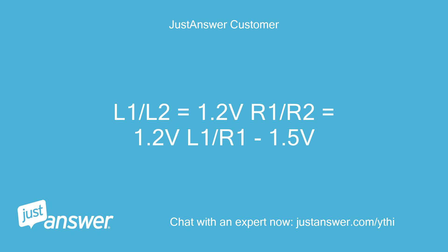Earlier you had stated that you had 63 ohms across the slip rings, which is good. But what I would like you to do is to leave the brush block installed, with the wires removed, and ohm across the brush terminals themselves. If you still get 63 ohms, the problem is most likely a burnt stator. If you get higher than 63 ohms, the problem is likely your brushes or slip rings.